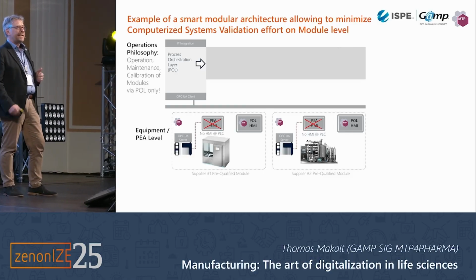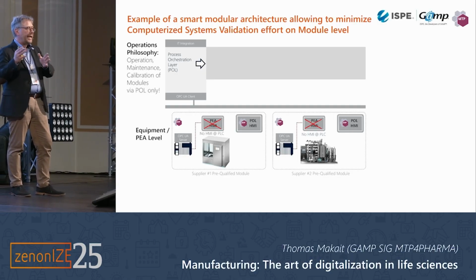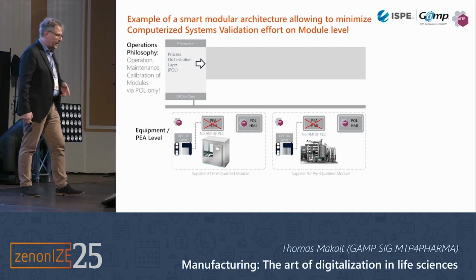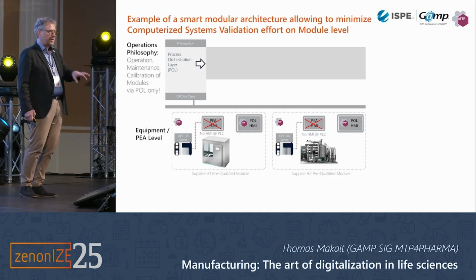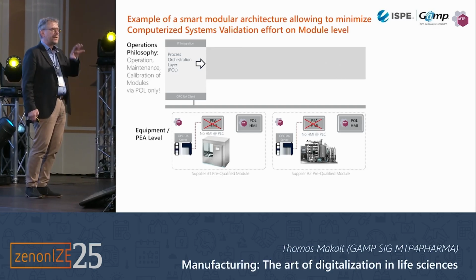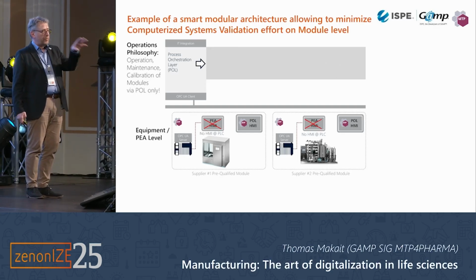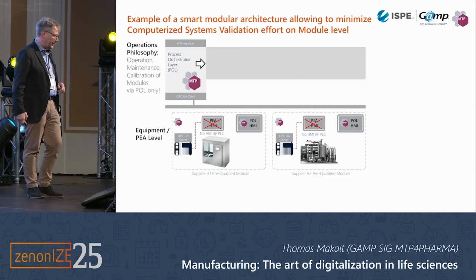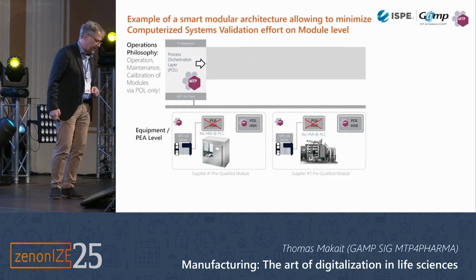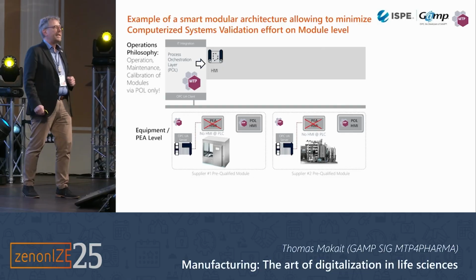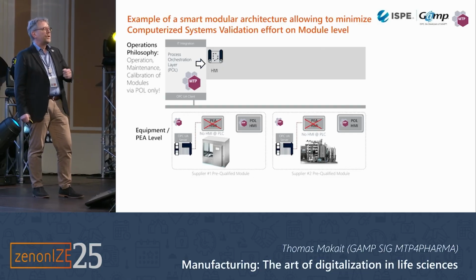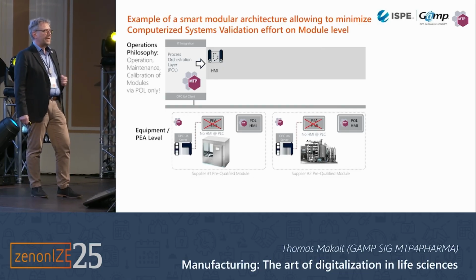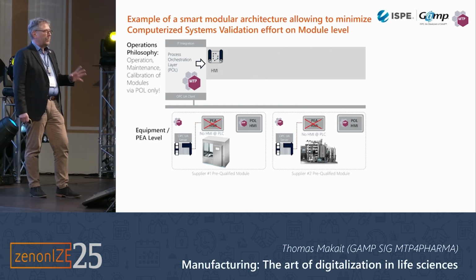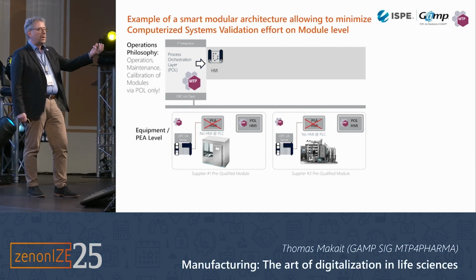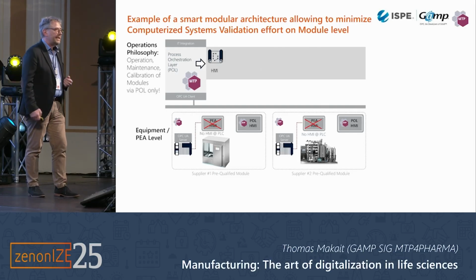And this is a nice thing — you're not hooked to any specific technology. Once you have asked a vendor to provide MTP-based automation with HMI screens for operation, maintenance, calibration, whatever, you import this MTP file into the POL, and you have the HMI there. There are even POL-as-a-service offerings available from a startup in Dresden, where you can use this POL to do an FAT, because the interface is defined in the MTP file.